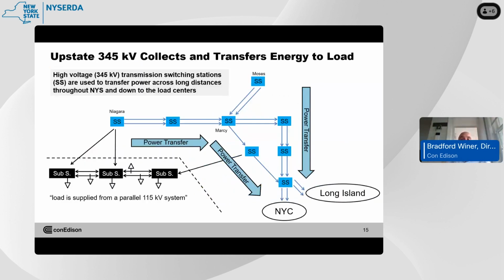Let's think about how New York State's transmission system was built generally. The boxes are laid out to resemble New York State. In less urban or dense environments, we typically use switching stations from the point of generation down into our load centers, then tap off those switching stations into substations that get down into load. So power transfers from west to center, north to south, and ultimately down to New York City and Long Island. Switching stations also include other equipment necessary for transmitting AC over long distances, such as capacitors and shunt reactors.